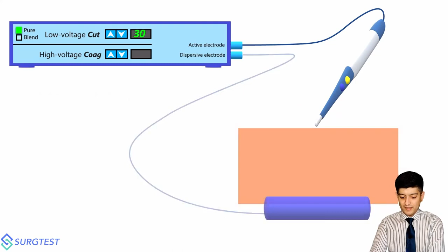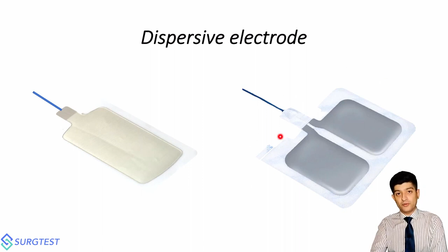So this is the dispersive electrode. And these are by and large the two types of dispersive electrodes that you're going to be seeing. You will either see a continuous plate which is there on the left side of your screen, or you'll have these split plate configurations. The split plate configuration is actually a safety mechanism. Say you have a dispersive electrode which has not been applied evenly to the patient. The ESU determines that the pad is now asymmetrically applied, which means the amount of current flowing between these two pads is not coming in evenly. So it automatically cuts off the power supply and it asks you to check how the dispersive electrode has been applied to the patient body. So if you ask me which one of these two is desirable, I would definitely choose the split pad electrode on the right of your screen.